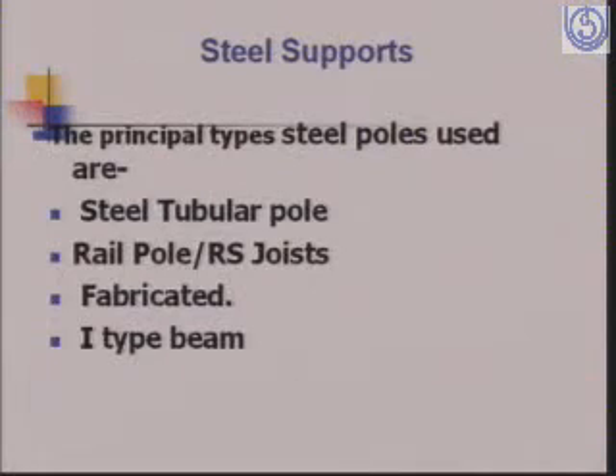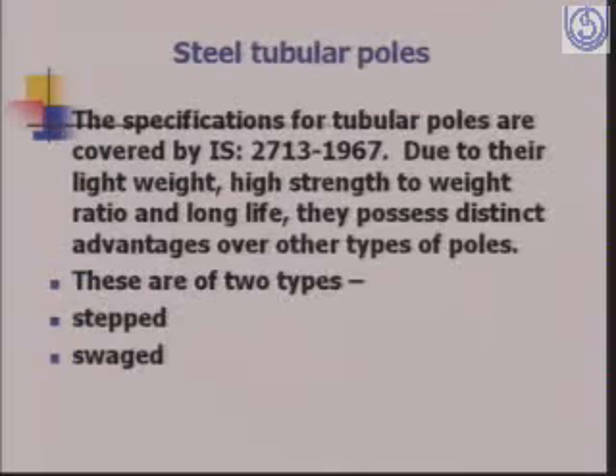Then we have poles of the steel type. The principal types of steel poles used are the steel tubular pole, the rail pole or the RS joist, the fabricated tower and the I-type beam. The specifications for steel tubular pole are covered in IS 2713, and due to their light weight, high strength to weight ratio and long life, they possess distinct advantages over other types of poles.